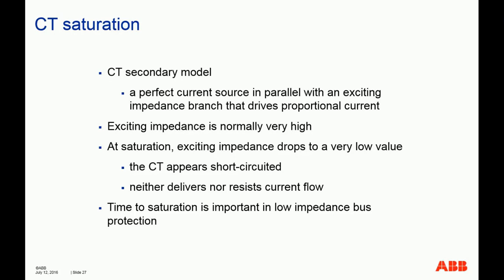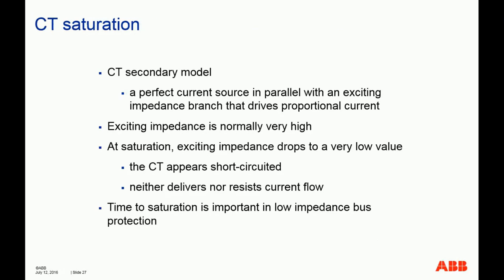If the CT saturates right away, let's say the CT wasn't sized or specified properly, chances of misoperation could happen, and then it could create disastrous consequences in terms of bus protection. So the bottom line is the CT needs to be properly sized and specified so that you give a couple milliseconds, because modern relays can handle up to 2 or 3 milliseconds of healthy secondary CT current waveform, so that the relay can make the correct decision to trip or not to trip.